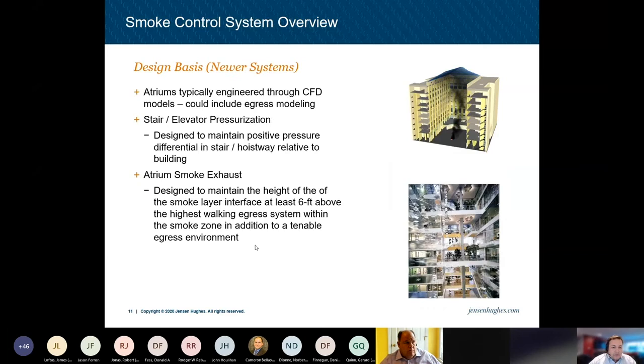So the design basis for newer systems, at least, the engineering has progressed over the years. Atriums, smoke exhaust, smoke control systems, they're typically engineered these days through CFD models, which could include egress modeling. Stair and elevator pressurization, those systems are designed to maintain positive pressure differential in the stair or hoistway relative to the building. They have varying performance requirements. So stair pressurization systems are designed with all of the doors closed. Elevator pressurizations are designed with all of the doors closed except for the floor of recall.